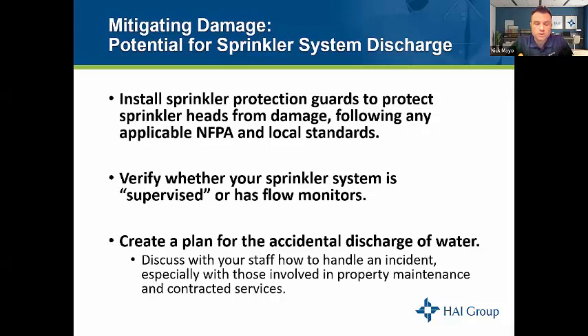So if your sprinkler system is what we call supervised, we want to make sure that someone is getting that flow monitor indicator, so that way a fire department can be dispatched. So even when there's a small bump in pressure in the system or a discharge of a sprinkler system and that flow monitor activates, that's what would activate the fire alarm system in the building, and either, depending on the recommendations that you have as a housing authority, people will shelter in place or evacuate the building, along with the fire department will start rolling to the scene to kind of figure out what's going on.